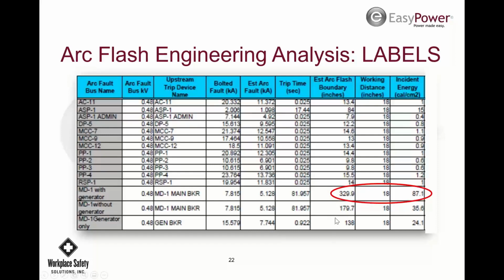So that's another reason why you want to look at the studies and have access to the studies, so you can have this spreadsheet, because you're looking at a label and you say, well, I can't go in there, got to shut it down. And that's all you needed to do is open the door from a distance and do an infrared test. Well, can't do an infrared test, it's too hazardous. Well, you can, if you lock out the generator, you can do it. Or if the generator's running, you lock out the utility, you can do it. But that's looking at the table.